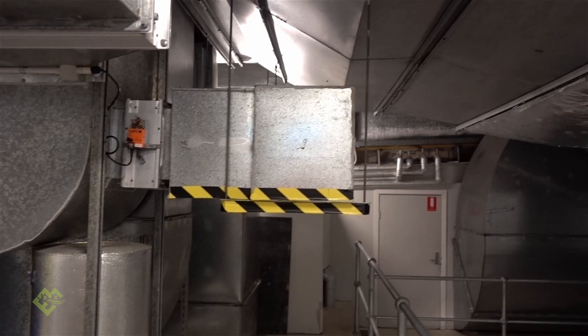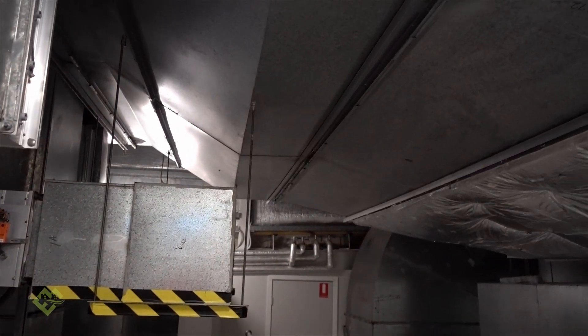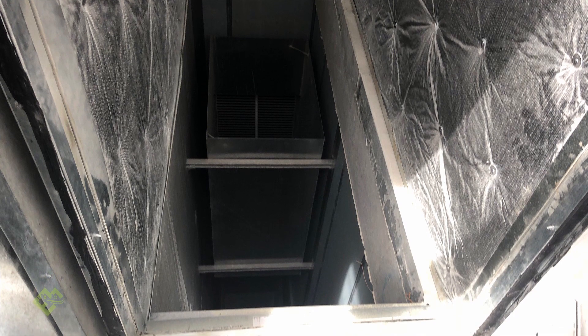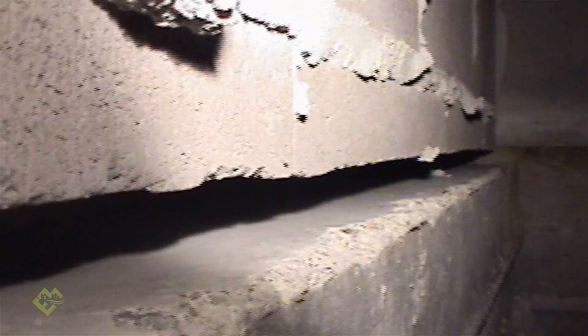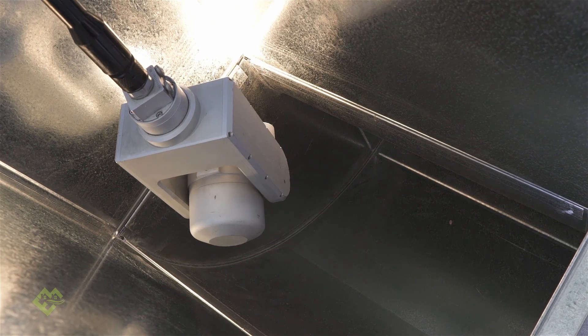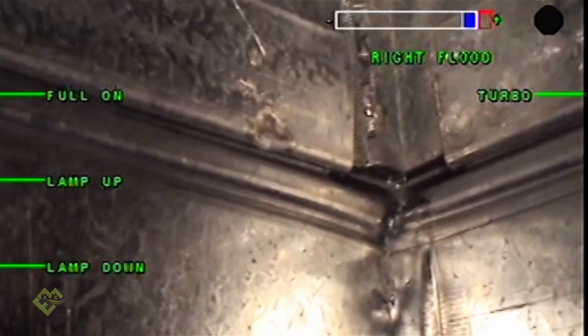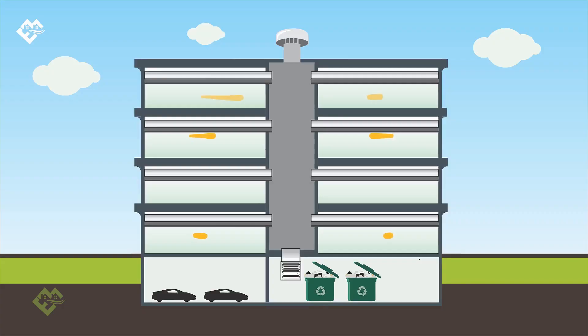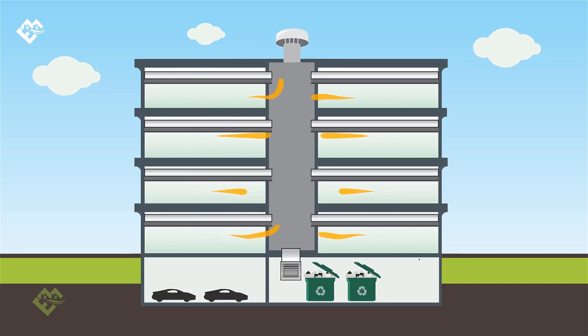What's usually the leakage rate for riser liners or speedwall risers? For those masonry or builder risers, they don't really have a standard dictating what level of leakage is required, but it can cause havoc if it's not done right. In some extreme cases we've worked on masonry risers where the system was very simple — a garbage room exhaust riser in a 25-storey building with one inlet and one outlet on the roof — and we got zero flow and zero pressure down at the garbage room, meaning it was more than 100% leakage.